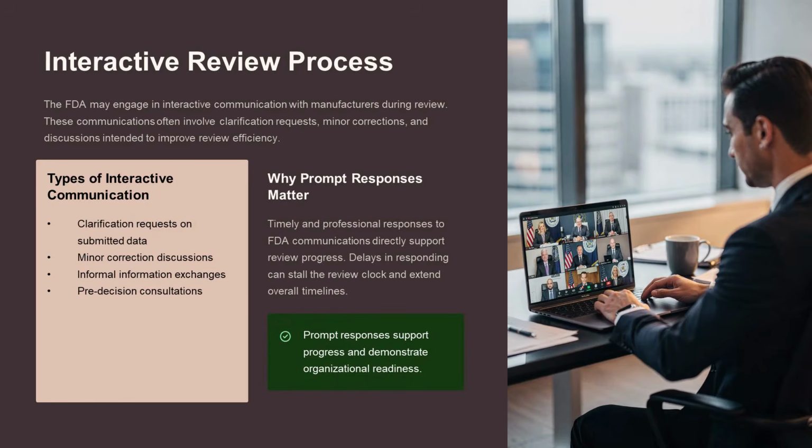The FDA may engage in interactive communication with manufacturers during review. These communications often involve clarification requests, minor corrections, and discussions intended to improve review efficiency. Timely and professional responses to FDA communications directly support review progress. Delays in responding can stall the review clock and extend overall timelines.